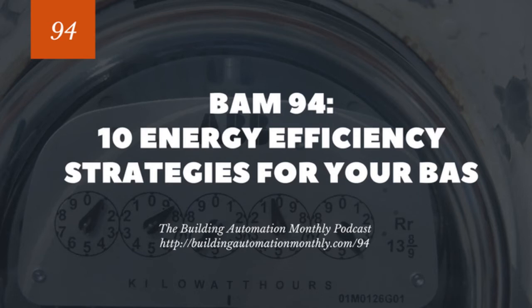Now, I talked about software overrides a little bit earlier in way number 3. Way number 6 is something that is very sneaky, and I see this happen quite often when I'm asked to go look at customer sites to give them an assessment as to how they can drive energy savings. They'll be so proud that they have no software overrides and that they're maintaining things. But then you get to the unit and you see the little Allen wrench key in the actuator and you realize that actuator's overridden, or the fan's overridden at the VFD, or a variety of things. I've even seen safeties jumped, which is horrible, but it's just the reality.